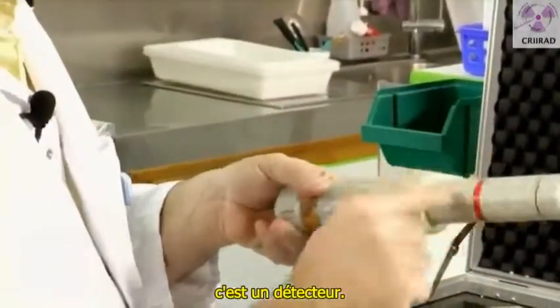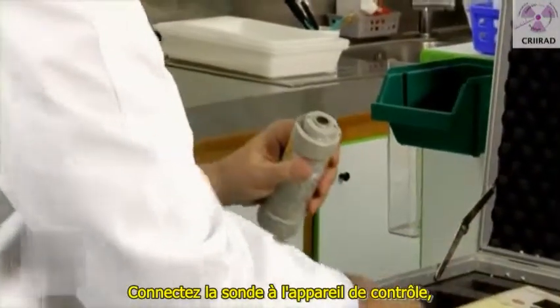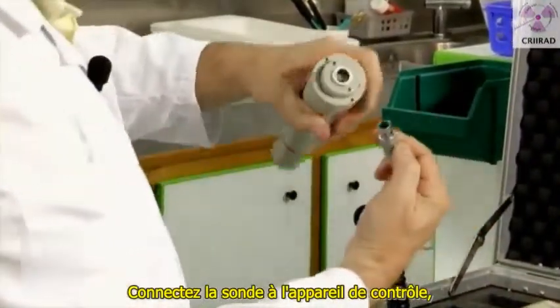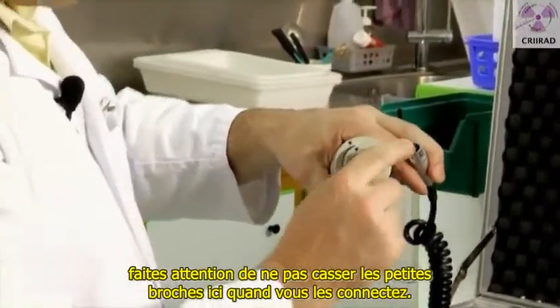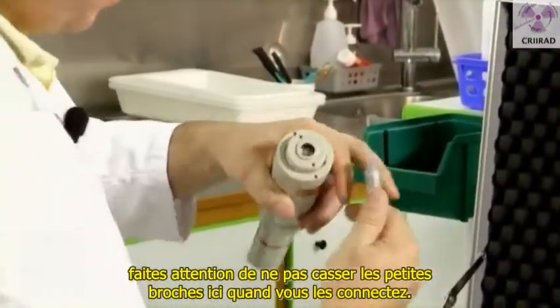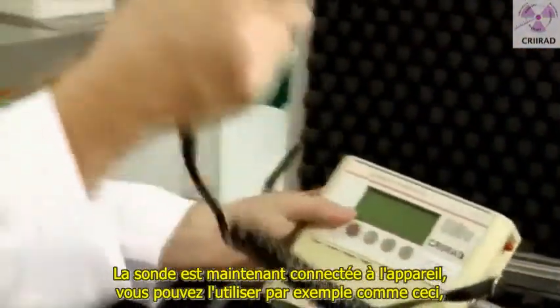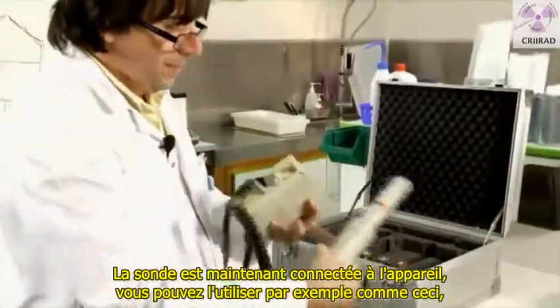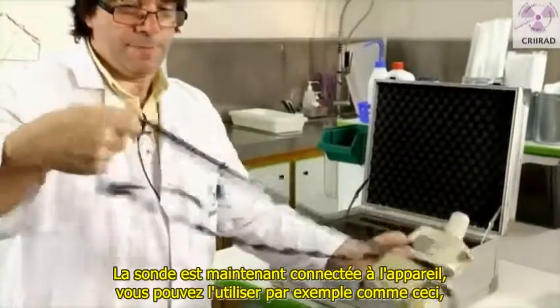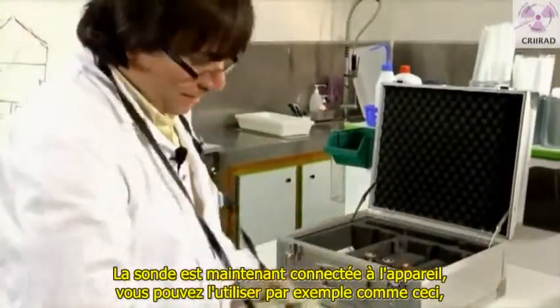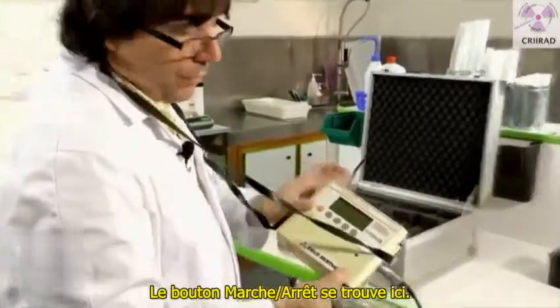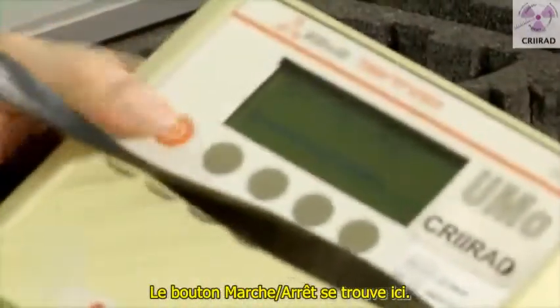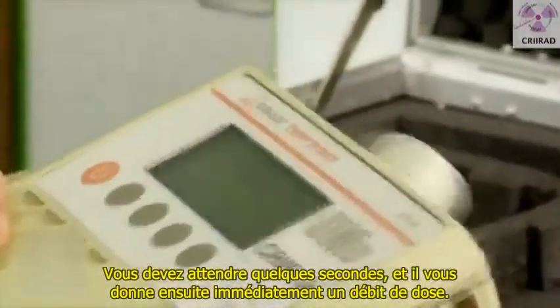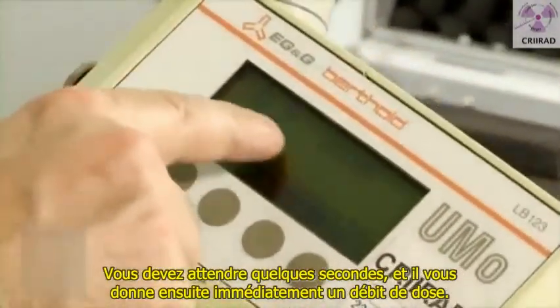This is a detector. To connect the probe to the monitoring device, be cautious not to break the very small pins here when you try to connect it. Okay, so now the probe is connected to the equipment. You can use it, for example, like that. Here is the on-off button. You have to wait for a few seconds, and it will immediately give you a dose rate.